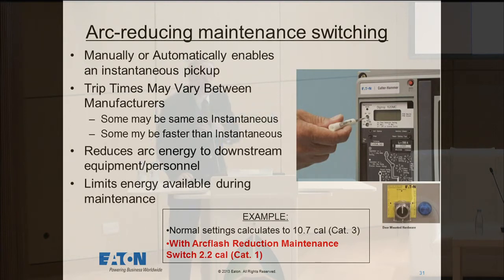My company makes this in many circuit breakers. We call it an arc reduction maintenance switch. And again, I mentioned that circuit breaker had a half-second delay, and that was done by the engineer to say, I want to make sure all breakers are set properly so that only the one closest to the fault opens. Settings on the breakers just right.